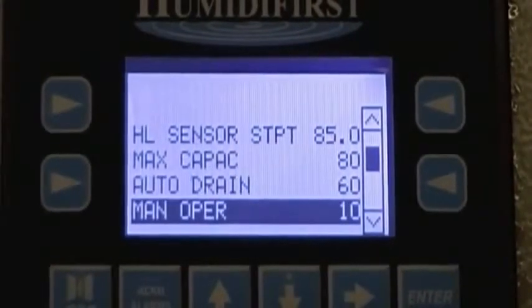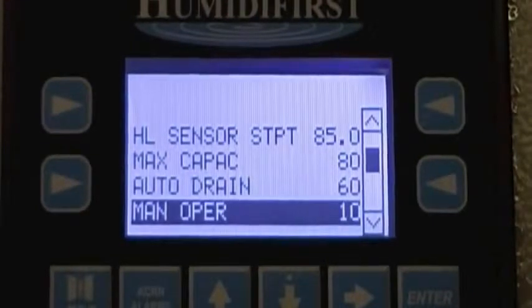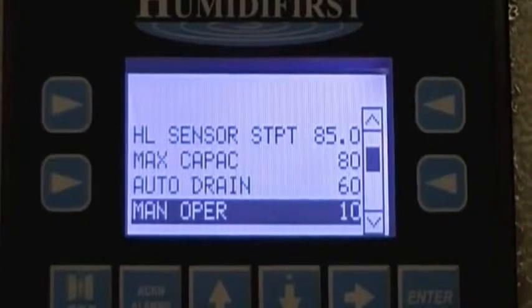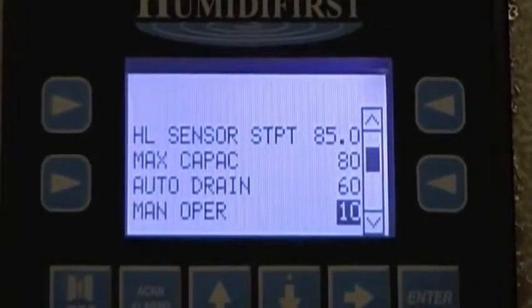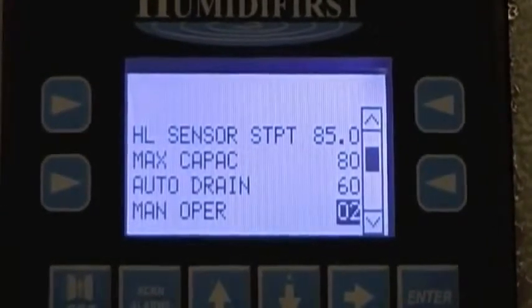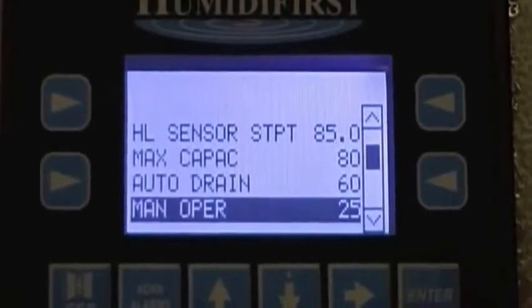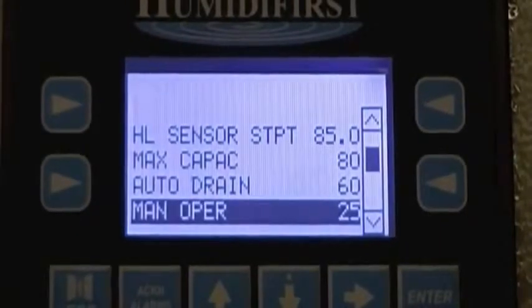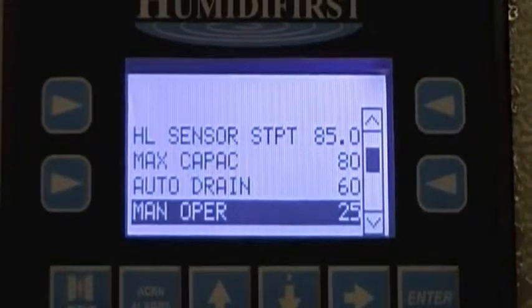If we scroll down to manual operation, this represents the number of minutes your humidifiers will remain in manual operation once you start it. The default setting is 10 minutes. We can change this to 25 by pressing enter until only the 10 is highlighted. Press 25 and press enter. The humidifiers will now remain in manual operation for 25 minutes upon engaging.